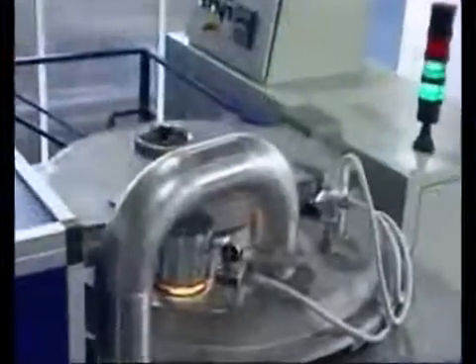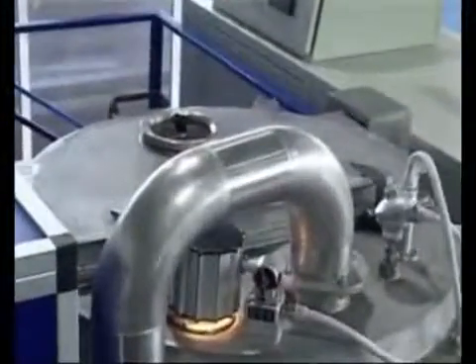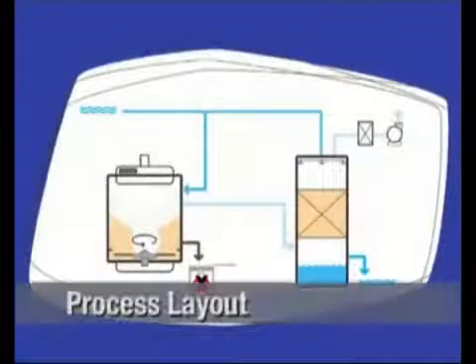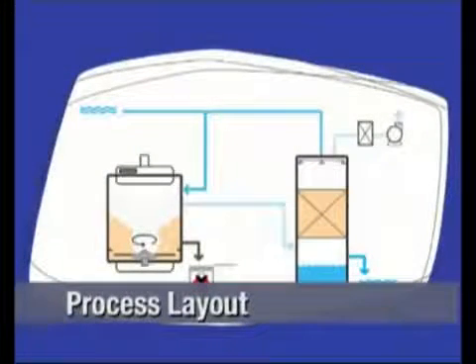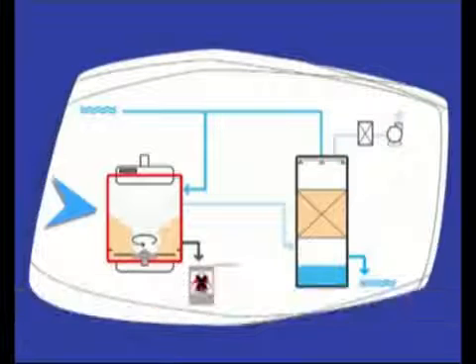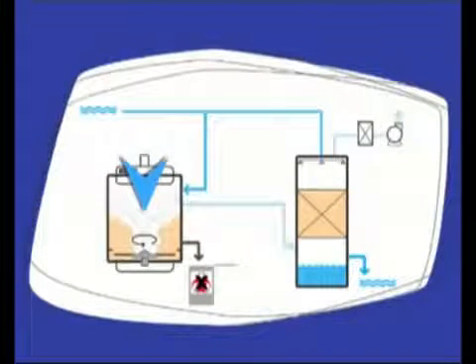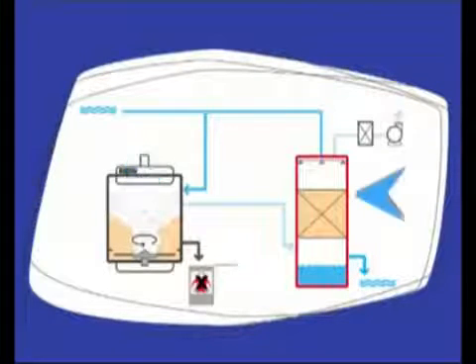The innovative character of the process is that sterilization is obtained in any case, no matter the type of waste. All processing is done inside the sterilization cell. Temperature is constantly monitored by an infrared reader, and a liquid disinfectant is used to sanitize the air tubes at the end of every cycle.